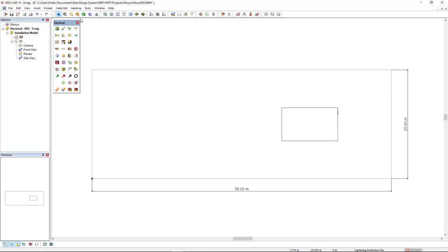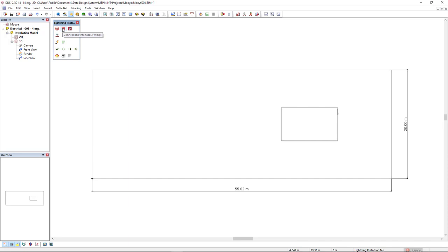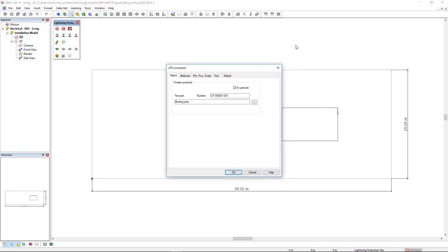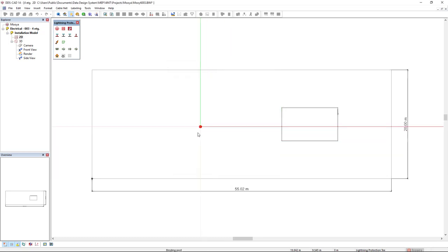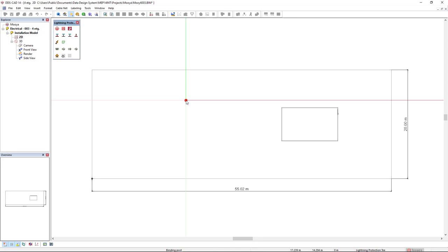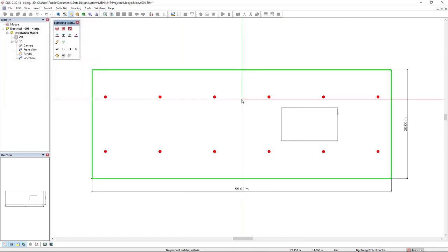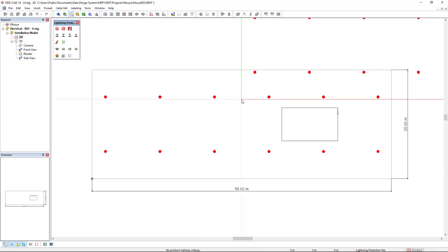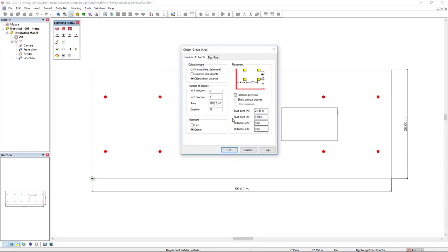Now, I will activate the lightning protection working mode and I will use this connections interface fittings function. I will use this binding post to create the cage and in the rod post scale tab, I will just increase the 2D symbol to be better visible in the floor plan, like this. I will insert this binding post as a group, so right mouse click and select the option place symmetrical on the surface and I will select the surface as indicated in green.